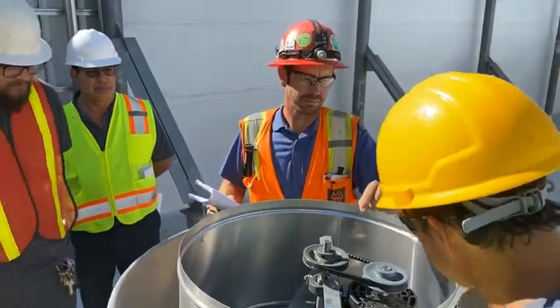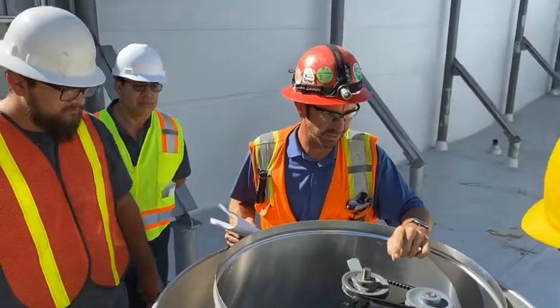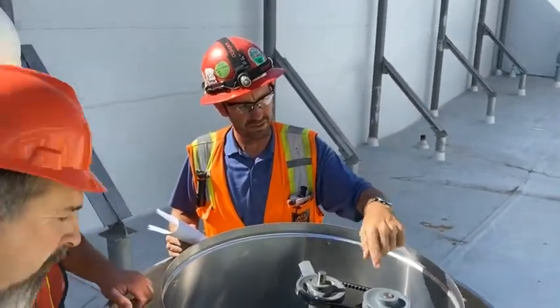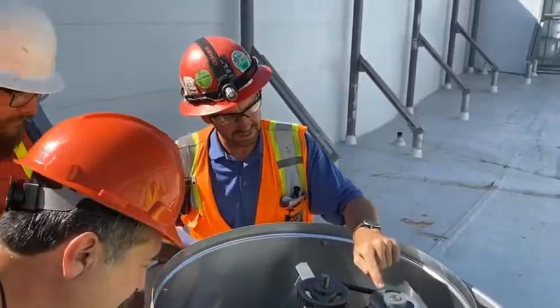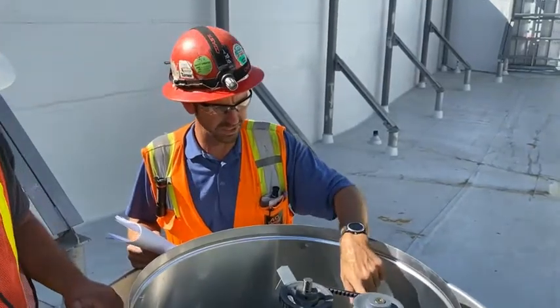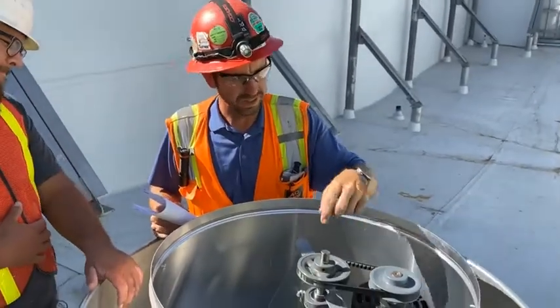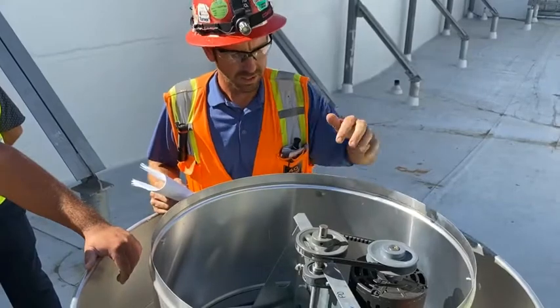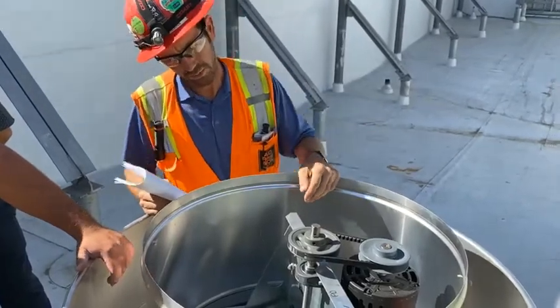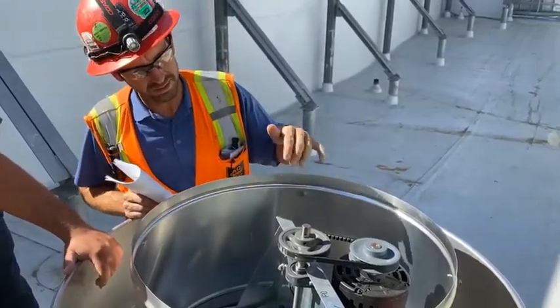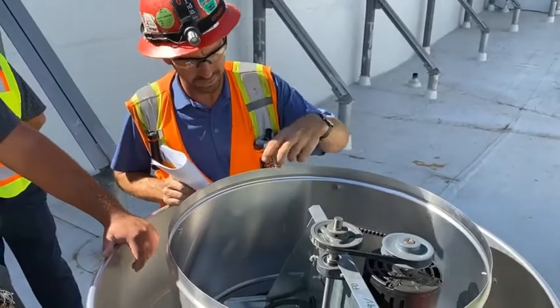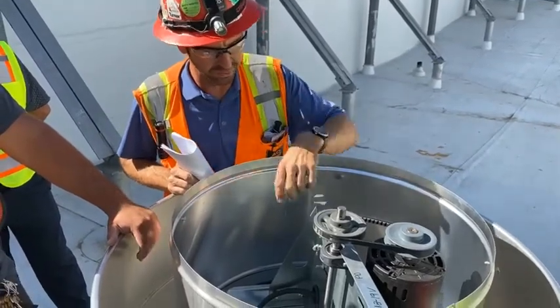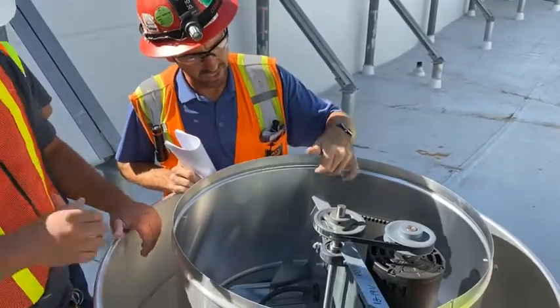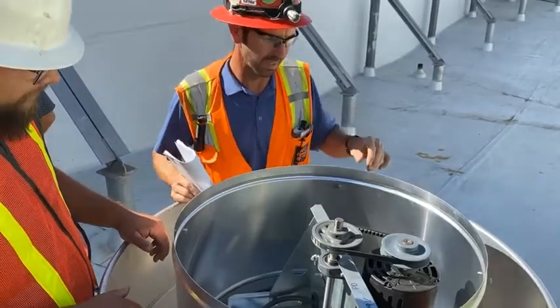All right. Okay. It is a belt-driven unit. We need to check set screws. We have the motor set screw, and then there's going to be a shaft set screw at the other side, and you have a shaft set screw right here. Quarterly, we're going to want to check the belts and all the bolts and hardware, to make sure nothing's vibrated itself loose. When you're doing the greasing, they should be checking all the bolts and hardware to make sure nothing's come loose.